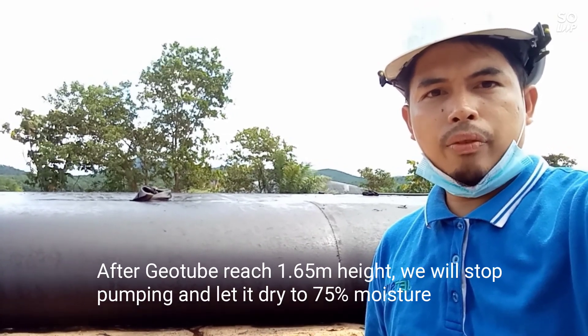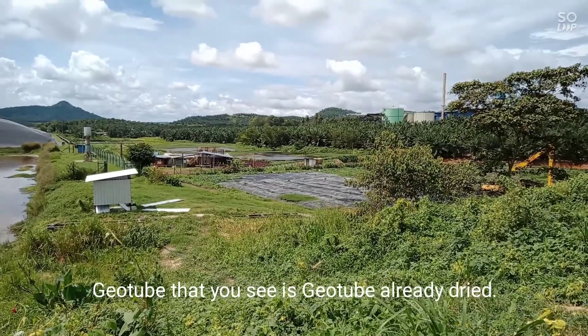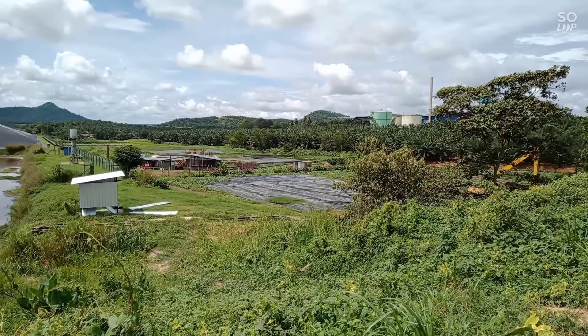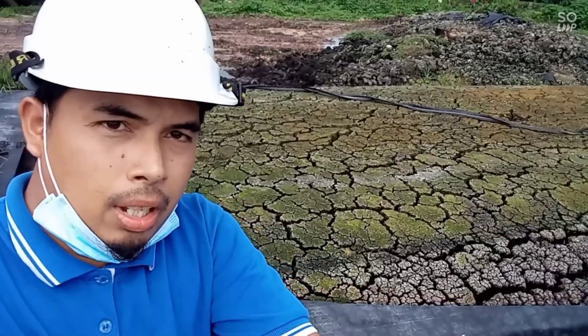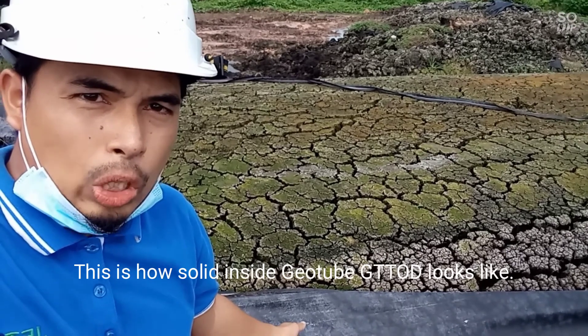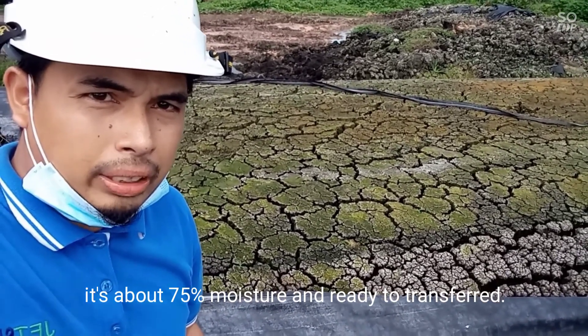After the Geotube reaches 1.65 meters, we will stop the pump and let it dry until 75% moisture. The Geotube you see here is already dry, and the solid inside is at about 75% moisture.